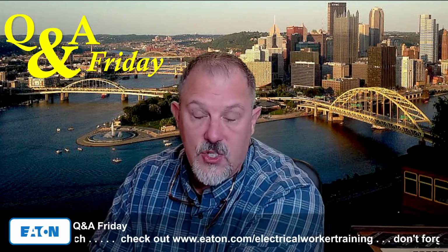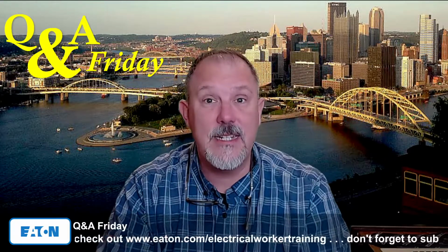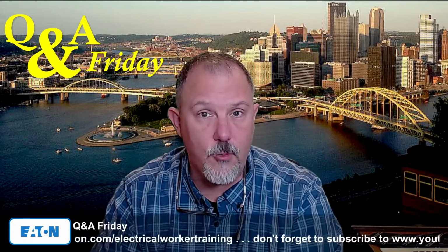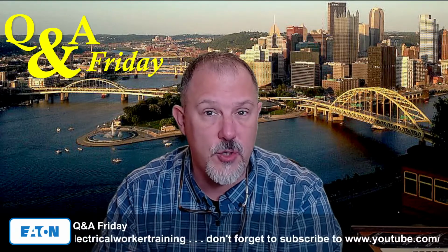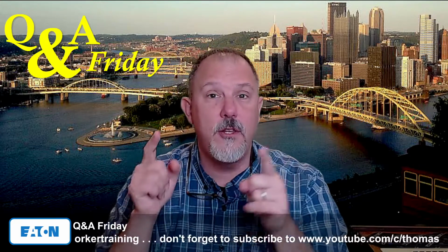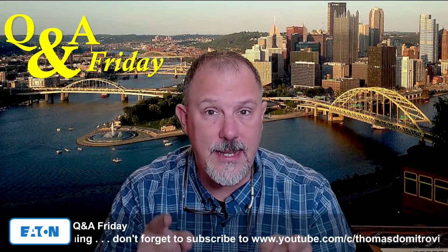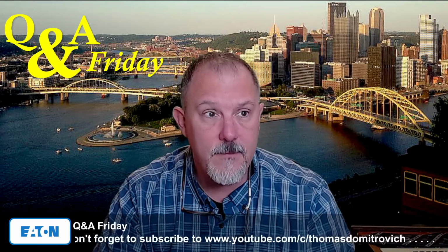So circuit breakers and a panel board, my message there is go back to the manufacturer, look at the standard, make sure it's a listed assembly. Look for that mark, the nationally recognized testing laboratory mark. Make sure it's authentic. Make sure that no modifications were made to the equipment after the fact. And if you don't like it, then put a ticket in with the nationally recognized testing laboratory.